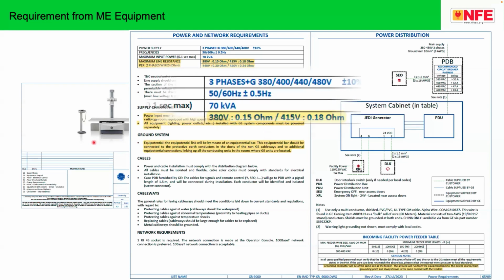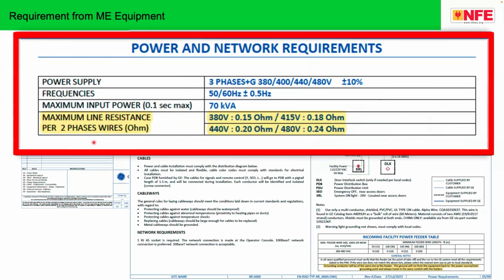Unfortunately, in India, there is a practice by the medical equipment suppliers. They ask for a separate earth electrode, and they ask for a less than 1 ohm earth electrode. Please note that nowhere in a medical electrical standard is a connection to a separate earth electrode required. The demand from the medical electrical, biomedical equipment companies is absolutely wrong.